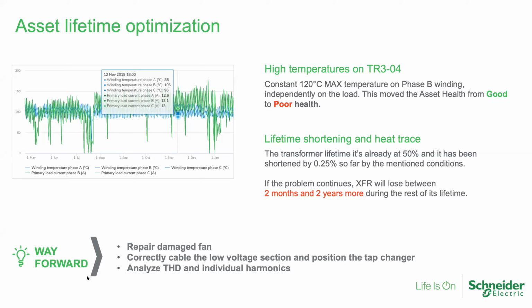So first we detected a high temperature, higher on one of the windings on phase B. Up to that point, just detecting a high temperature triggered by a threshold, and recording and trending it, is something any HMI, SCADA, or historian can do. There's nothing fancy about it, any piece of software can accomplish that.